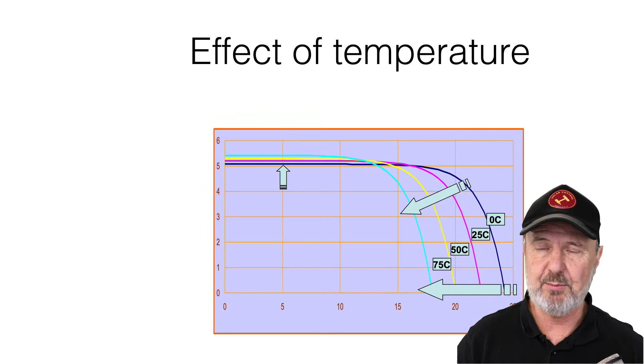Conversely, the colder they get, the more power they produce because they produce more voltage. Now that's a good thing if you're lucky enough, but it is a consideration in terms of safety. The equipment you connect it to must be able to cope with that higher voltage under cold conditions. It might be quite fleeting though. You might find that just first thing on a cold frosty morning, the sun comes through the fog at around 10 o'clock, the panels are at 0 degrees, the sun hits them, and you get the maximum voltage for a few seconds. Does it damage any of the equipment? Does it exceed the rating of switchgear, cables, isolators, etc.? So that's really more of a concern for selecting product than actually getting a bonus of power production. But if you happen to live somewhere where it's 0 degrees, good on you - you'll really get a lot more power out of your panels.